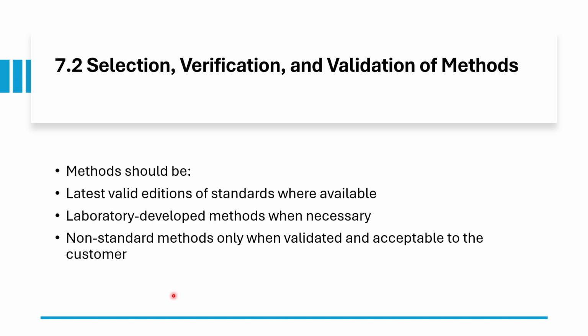Now before introducing any method, the laboratory must verify it can properly perform the method. Non-standard methods and laboratory developed methods must be validated to confirm they are fit for the intended use. Validation must be as extensive as necessary and include parameters such as measurement range, accuracy, precision, detection limit and robustness.